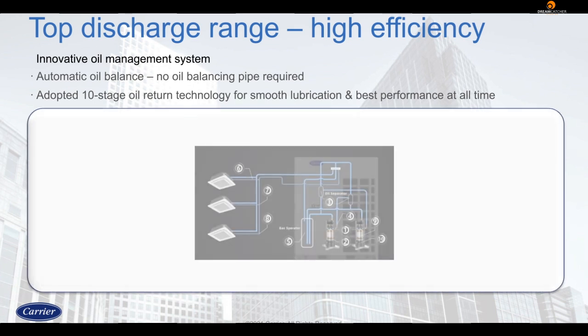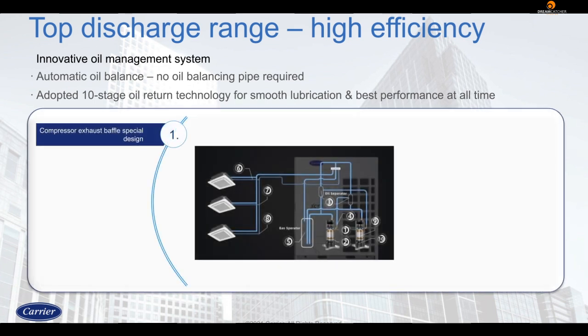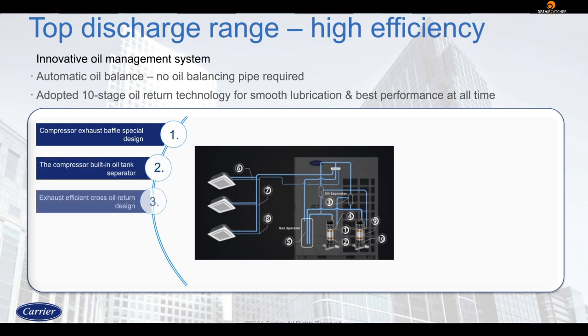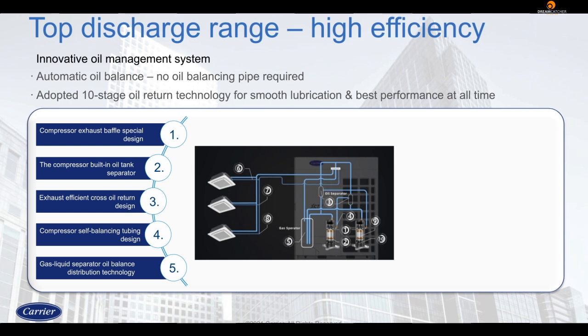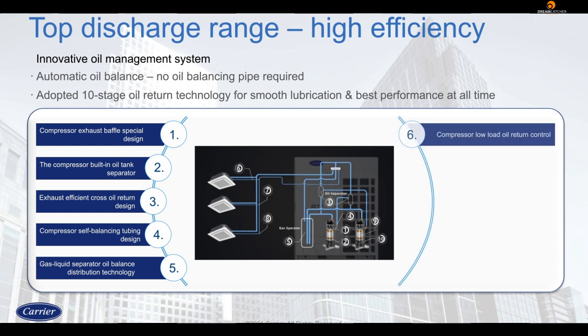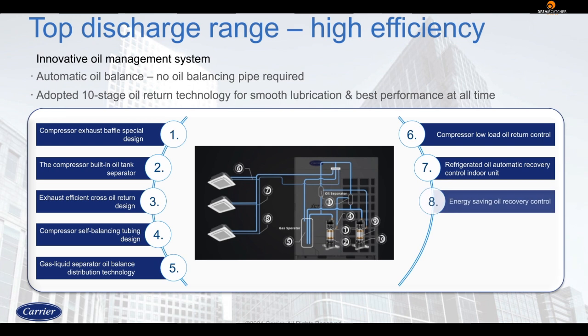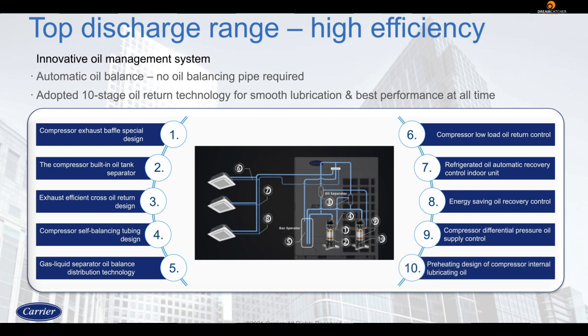This setup comprises of compressor exhaust baffle special design, compressor built-in oil tank separator, exhaust efficient cross-oil return design, compressor self-balancing tubing design, gas liquid separator oil balance distribution technology, compressor low-load oil return control, refrigerated oil automatic recovery control indoor unit, energy saving oil recovery control, compressor differential pressure oil supply control, preheating design of compressor internal lubricating oil.